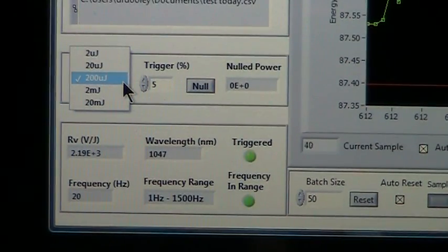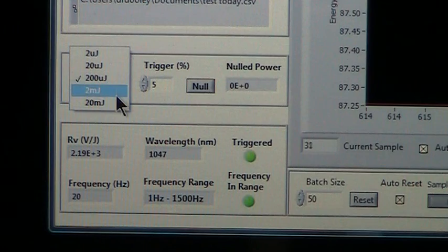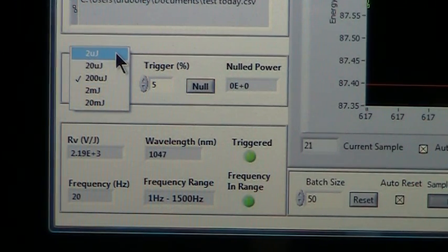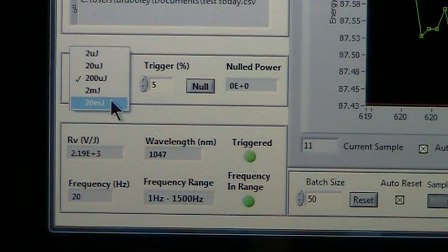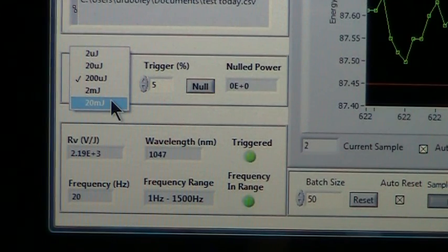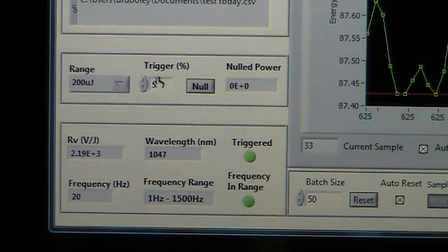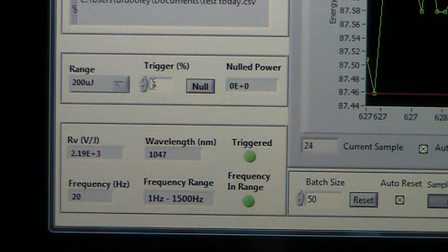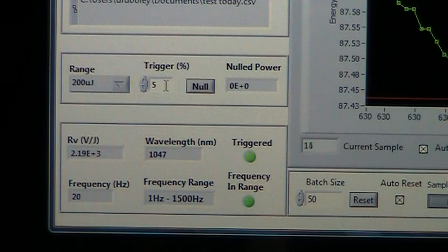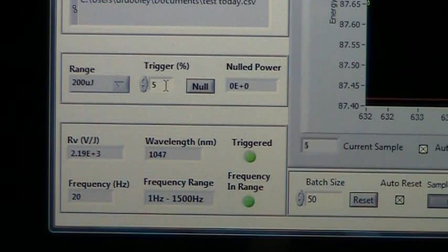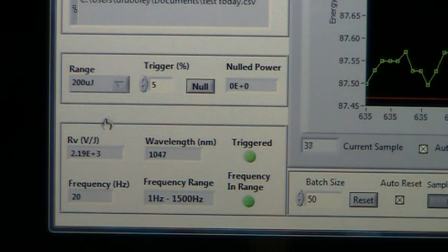You click on that and you can manually range the instrument from 2 microjoules to 20 millijoules for this particular DPJ joule meter. To the right of that is a trigger window. This allows the user to set the trigger anywhere from 2 to 20% of full scale. We're set at 5 right now.